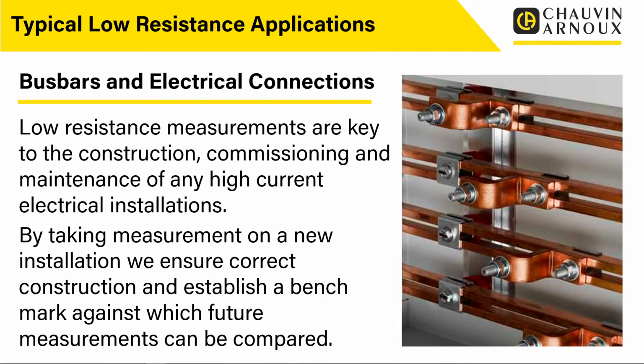from one busbar to the next, or we can have specific values that we know we need to achieve to make sure that we're getting a good electrical connection. And this is good during the construction process to make sure we've made these connections properly. We've used good workmanship and good standards. But also those values can then be used down the line when we come to do maintenance, to see if these things have increased.